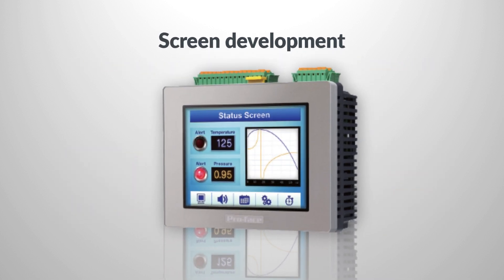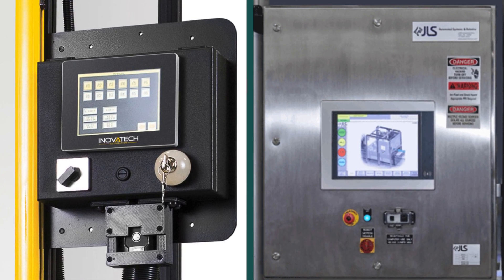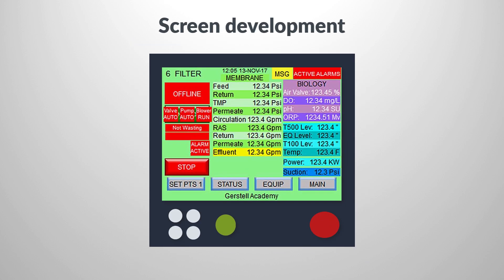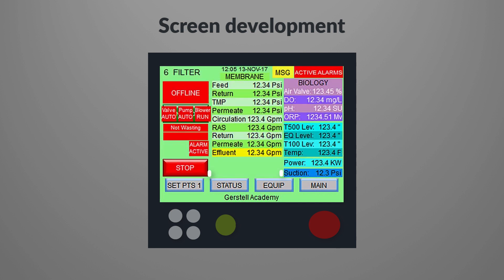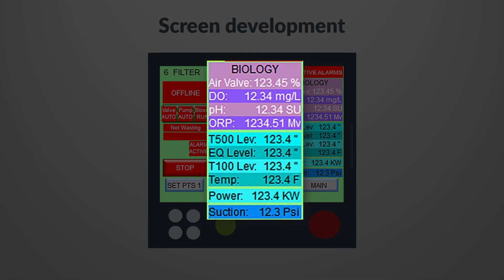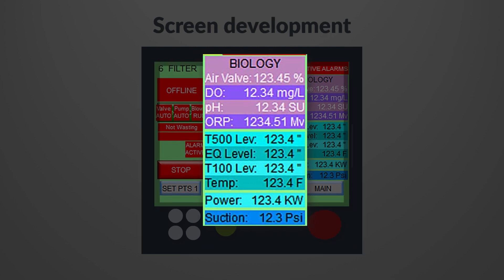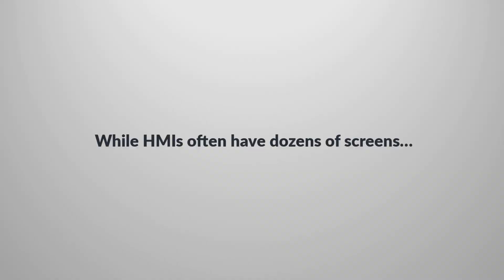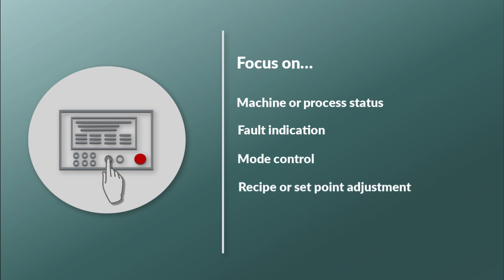When it comes to developing graphics screens, there are many basic HMI design techniques that should be followed. But an operator interface is more than just a pretty picture — that pretty picture may have too much information. Be sure to create logical zones on an HMI screen and limit these zones to five or seven. Create columns or put boxes around each zone and include clear, large text to identify it. Limiting the number of colors used and simplifying the navigation can also make for a better HMI. While HMIs have dozens of screens, focus on machine or process status, fault indication, mode control, recipe or set point adjustment, and manual functions.